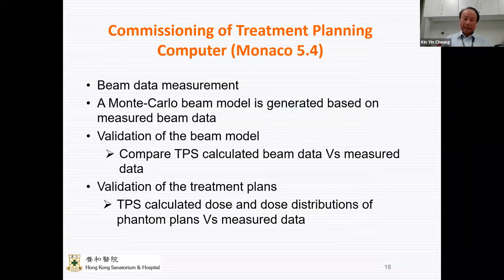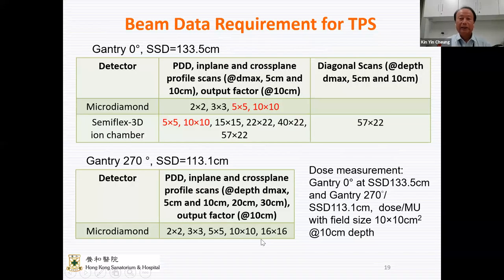Okay, in commissioning the planning computer, as I said, we have to measure the beam data and then send the beam data for modeling. And then we do the validation of the beam calculation and treatment plan delivery. The beam data required is not too many. We have to measure the percentage depth dose and field profile in plane and cross plane at three different depths for field sizes ranging from 2x2 up to the maximum of 57x22.